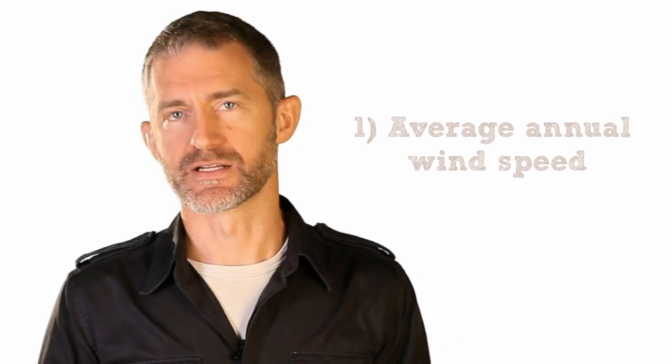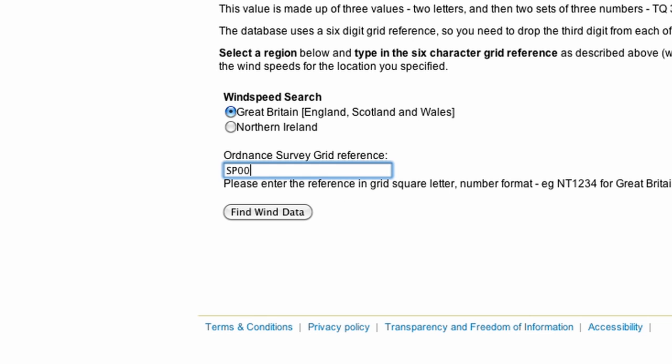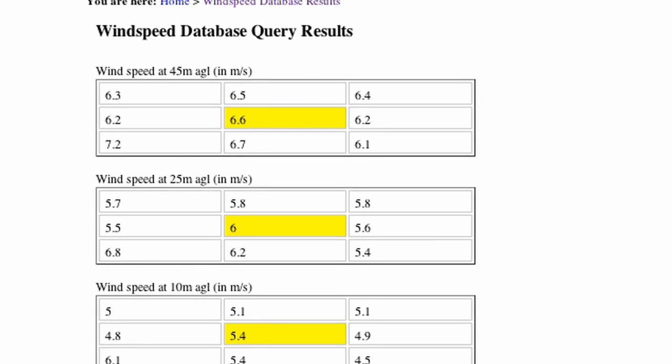If you're going to investigate wind, there are some questions that you can answer for yourselves before you need to hire a consultant. What is the approximate average annual wind speed at your prospective site? You can find this out online using the NOABL Wind Speed Database. This is a rough guide only, but if it shows 6m per second or more at 45m above ground level, then it's worth investigating further.